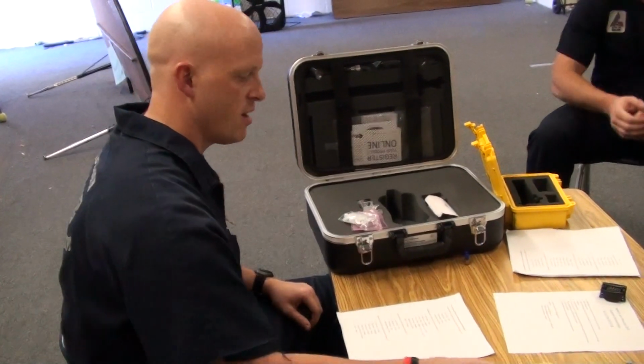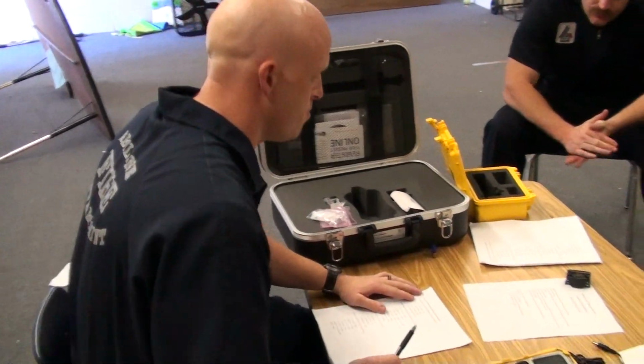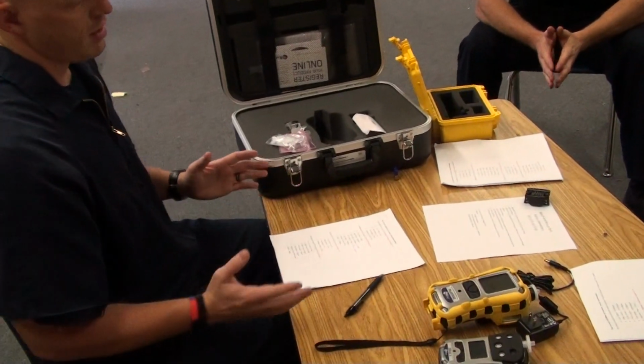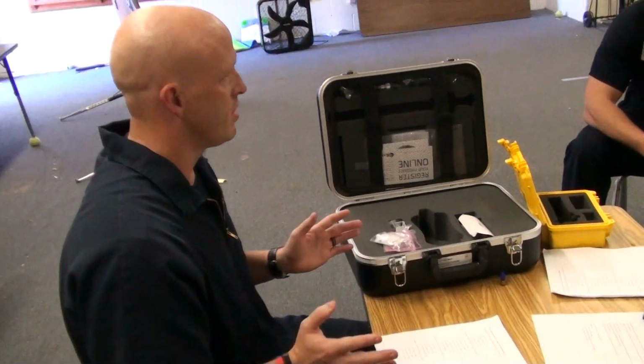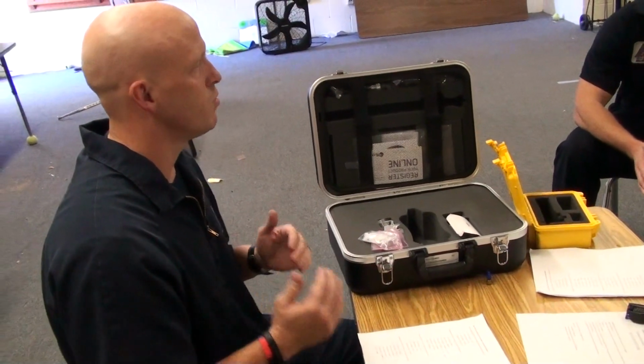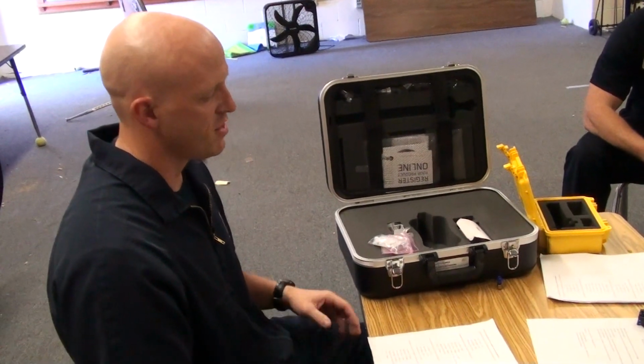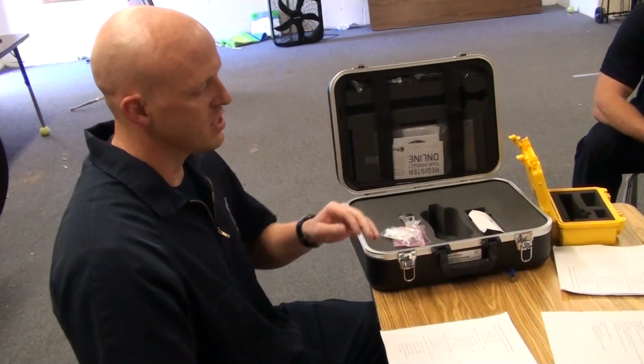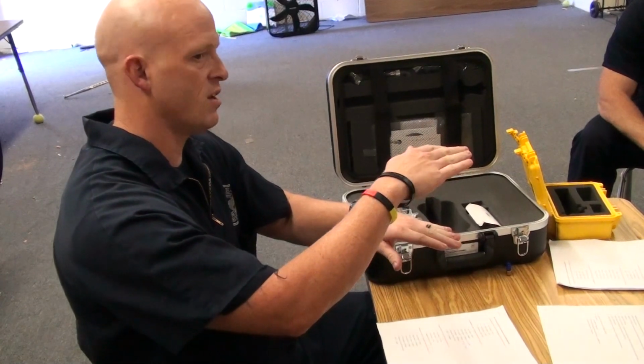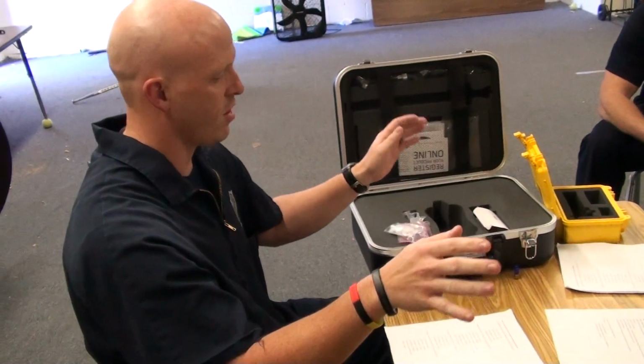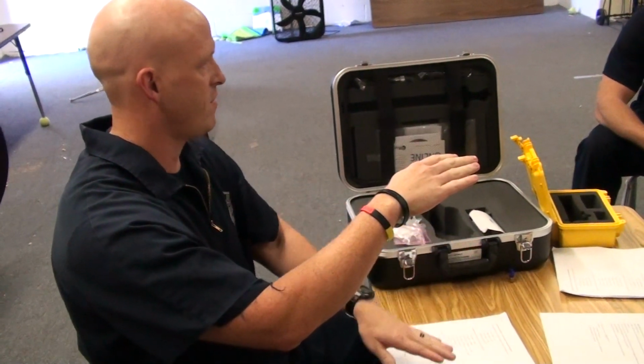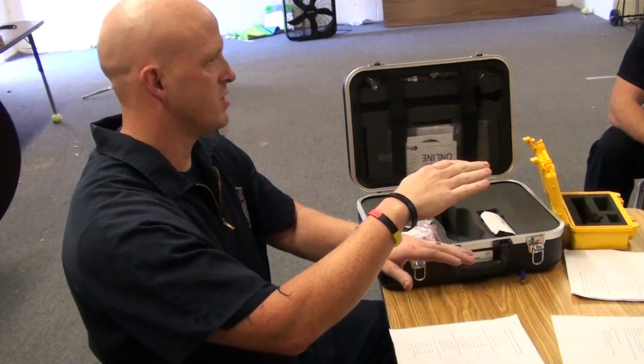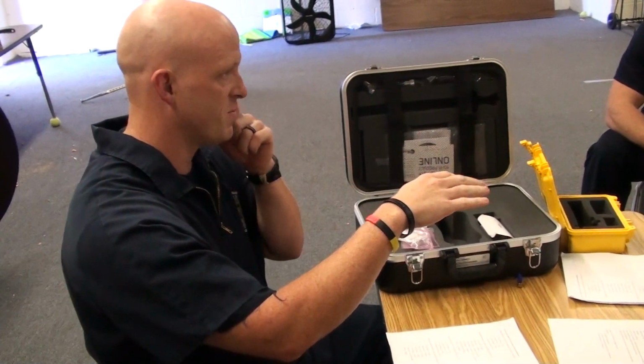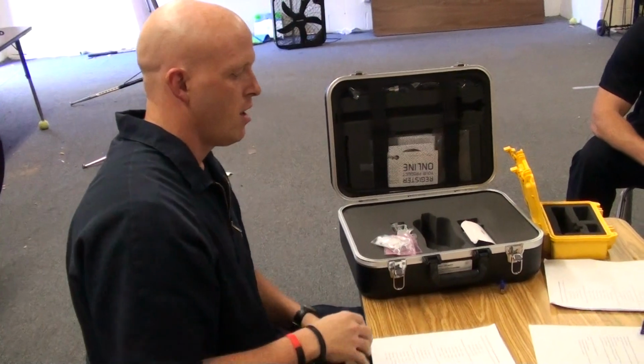On both of them, the LEL is set to methane, and no matter what kind of gas it's reading, any combustible gas, it's going to assume it's methane, because that's what it's set to. Methane's flammable range is from 5% to 15% of all the air out there. So if it's not enough, it's too lean. If it's above 15%, it's too rich and it's not going to burn.